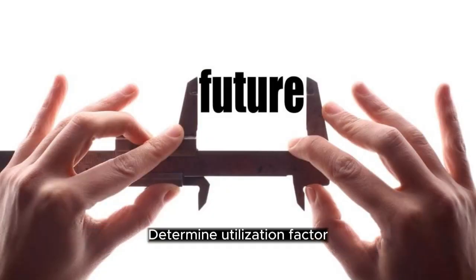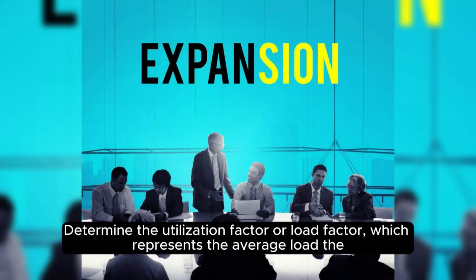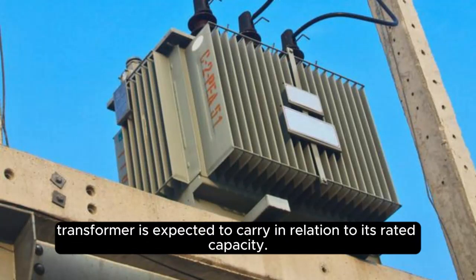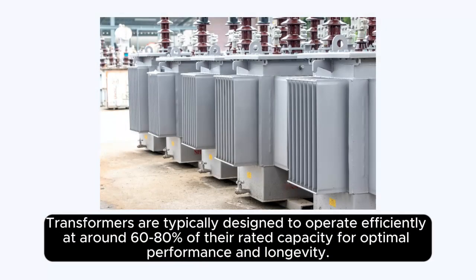Determine utilization factor. Determine the utilization factor or load factor, which represents the average load the transformer is expected to carry in relation to its rated capacity. Transformers are typically designed to operate efficiently at around 60–80% of their rated capacity for optimal performance and longevity.